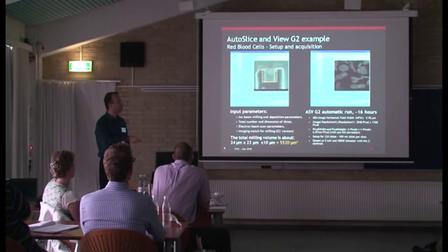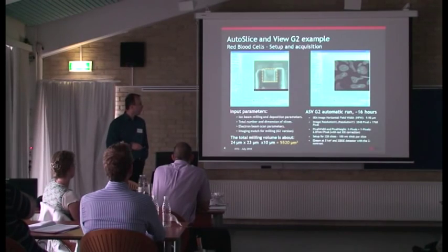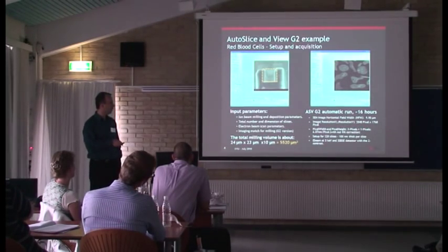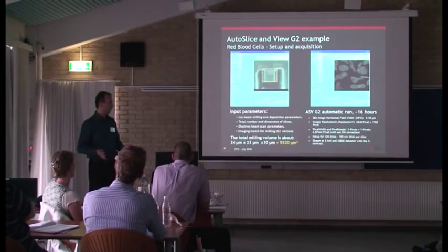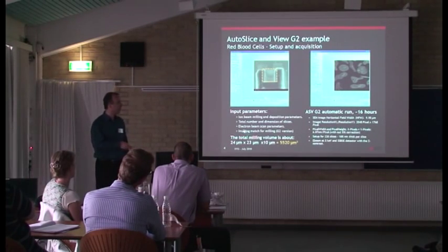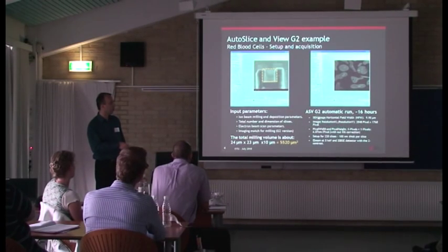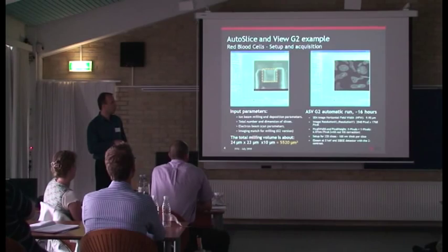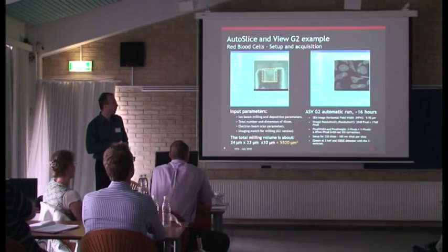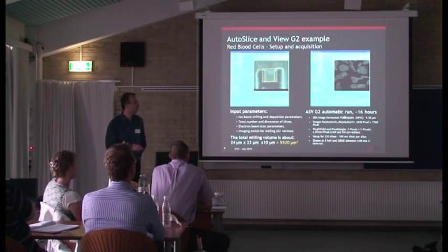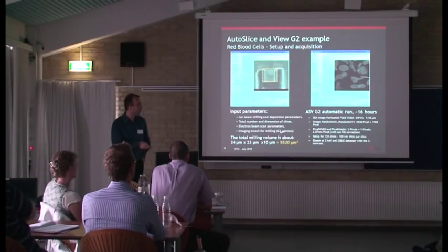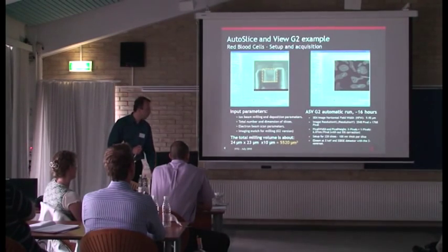So here you can really go through each individual slice that you can acquire with the DualBeam. In terms of volume, also just to set expectations, this is a really classic volume in terms of time to results, typically 20 by 20 by 10 microns. And also the image resolution here was chosen to be approximately 2000 pixels by 1700, meaning we get something like 6 nanometers per pixel within the image, working again with backscatter imaging.